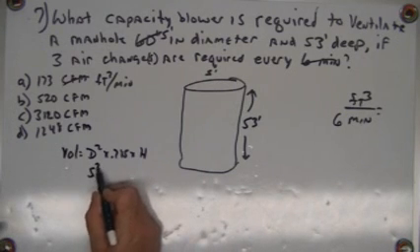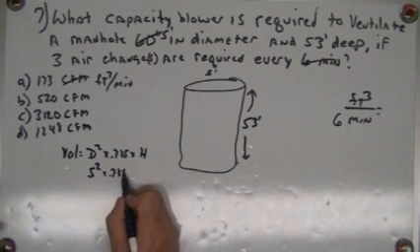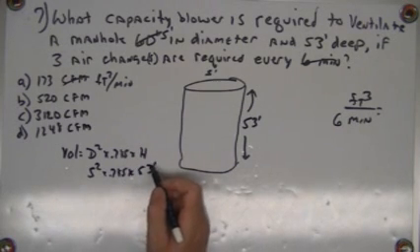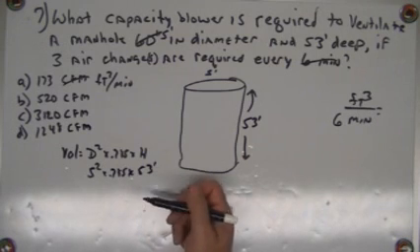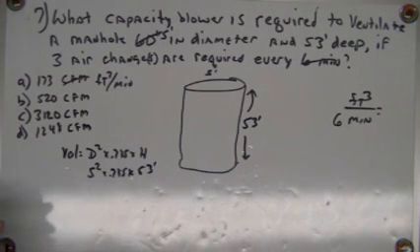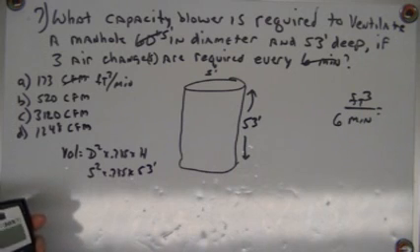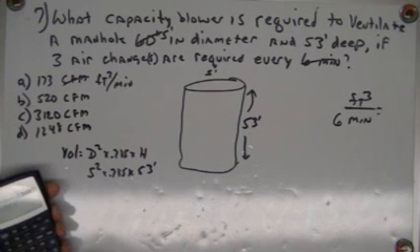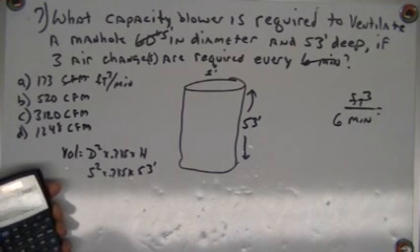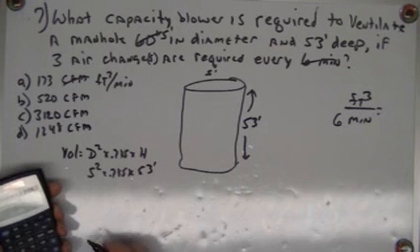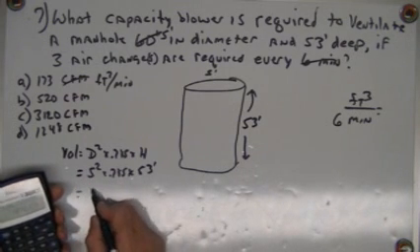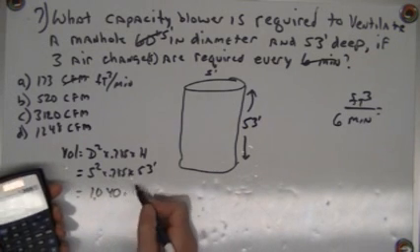So I'm going to go 5 squared times 0.785 times 53 feet. Let's see here, 5 times 5 times 0.785 times 53, and that's going to give me 1040.125, that's close enough.